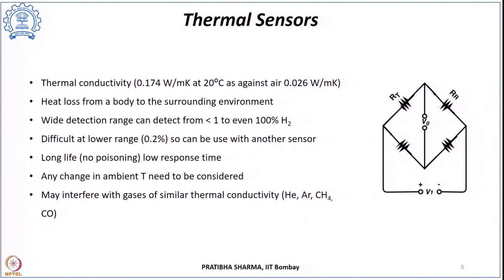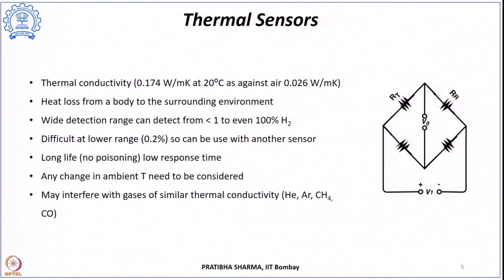These thermal conductivity-based sensors have a wide detection range — from less than 1% to even 100% hydrogen. However, they cannot detect below 0.2%, so another sensor must be used alongside for lower concentrations. Since these sensors are not poisoned by hydrogen or other gases, their operational life is long — more than 5 years — and response time can be as low as 5 seconds.